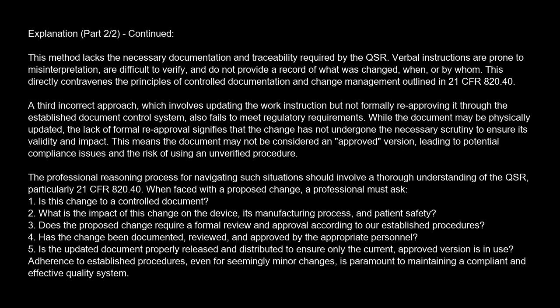using an unverified procedure. The professional reasoning process for navigating such situations should involve a thorough understanding of the QSR, particularly 21 CFR 820.40. When faced with a proposed change, a professional must ask: 1. Is this change to a controlled document? 2. What is the impact of this change on the device, its manufacturing process, and patient safety? 3.